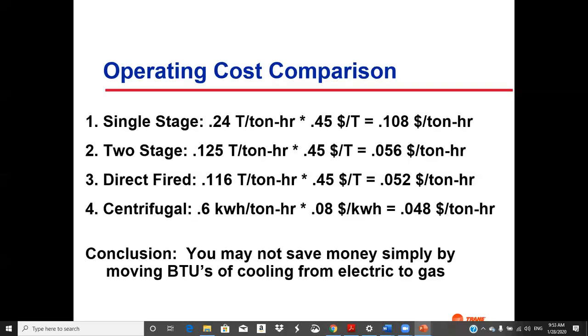I want to pick up and finish the presentation we were in last time. This is on the economics of absorption refrigeration, and we had just gotten down to where we had calculated the operating cost for the various types of chillers. So single stage absorber, it was 0.24 therm per ton hour, and a therm is 100,000 BTUs, and a ton hour is 12,000 BTUs of refrigeration. And our price was 45 cents a therm, or $4.50 a million BTUs. And so we went down through all of this.